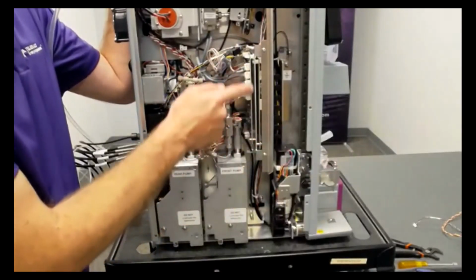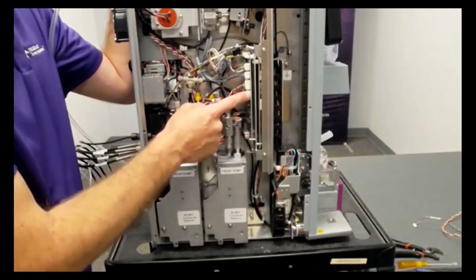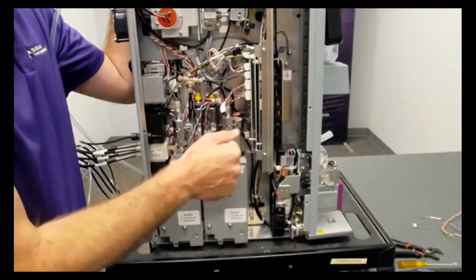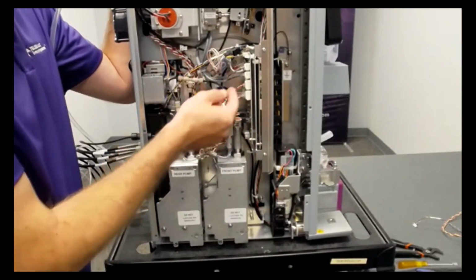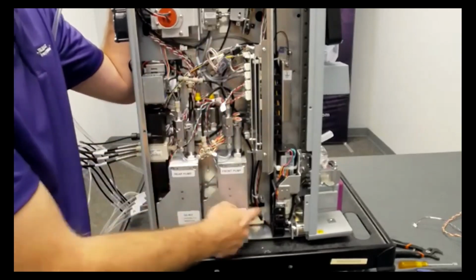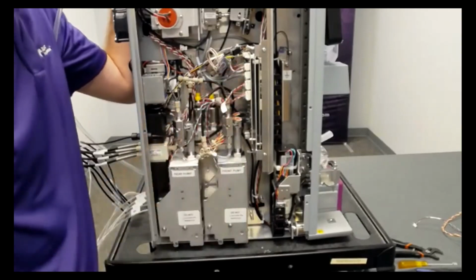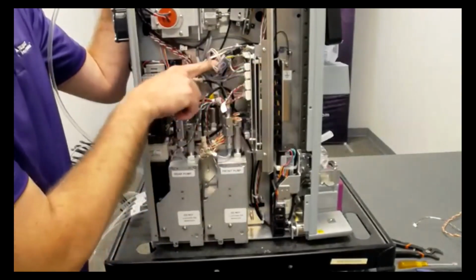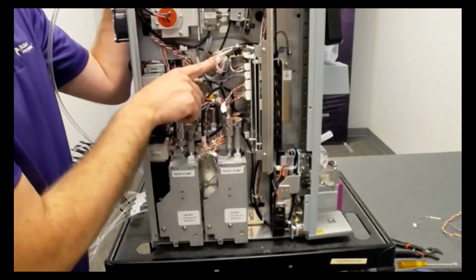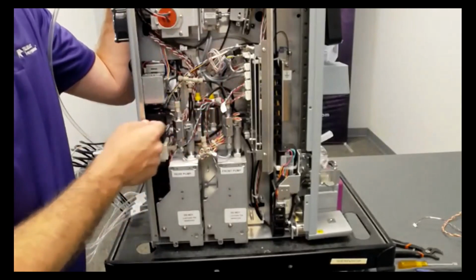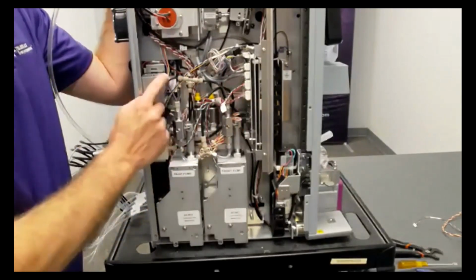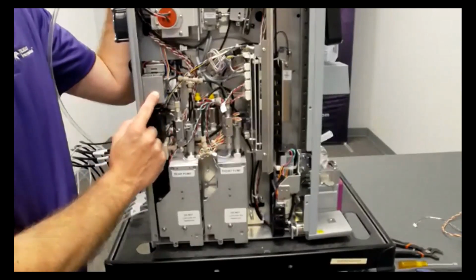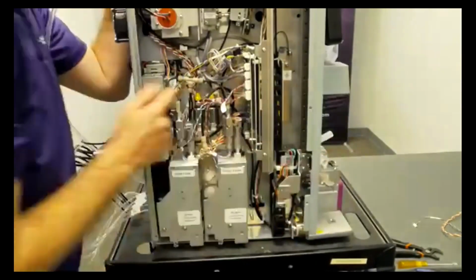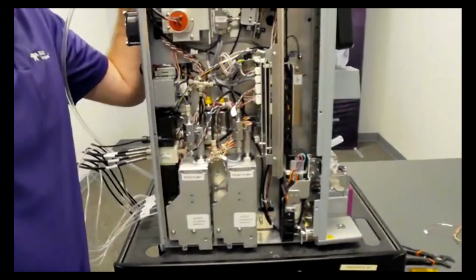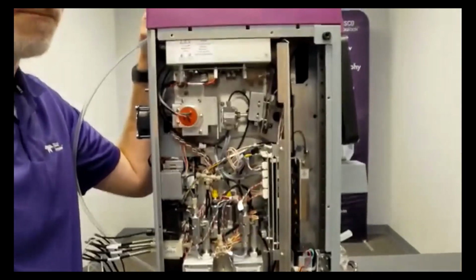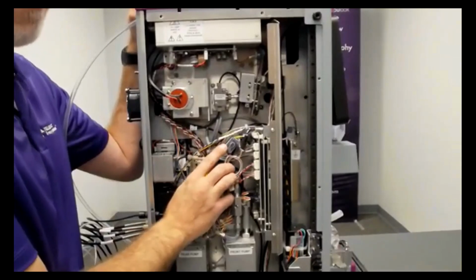Pump boards, we call them. But these are kind of like the control boards in our older unit, but I think they're way cooler. So you hook up the pumps, the sensors, transducers. If you have a vapor sensor down here, which this unit does not, it plugs into this board as well. A lot of stuff plugs into this board. 3-way valve for if you have ELSD, and it helps set up your path through the system. Okay, that all plugs in here. You can't see it, but behind here is the left-right motor for your fraction arm to move. Okay, that's this motor right here. Moving up just a little bit. I said it already, you can barely see it, but there's a 3-way valve right here.